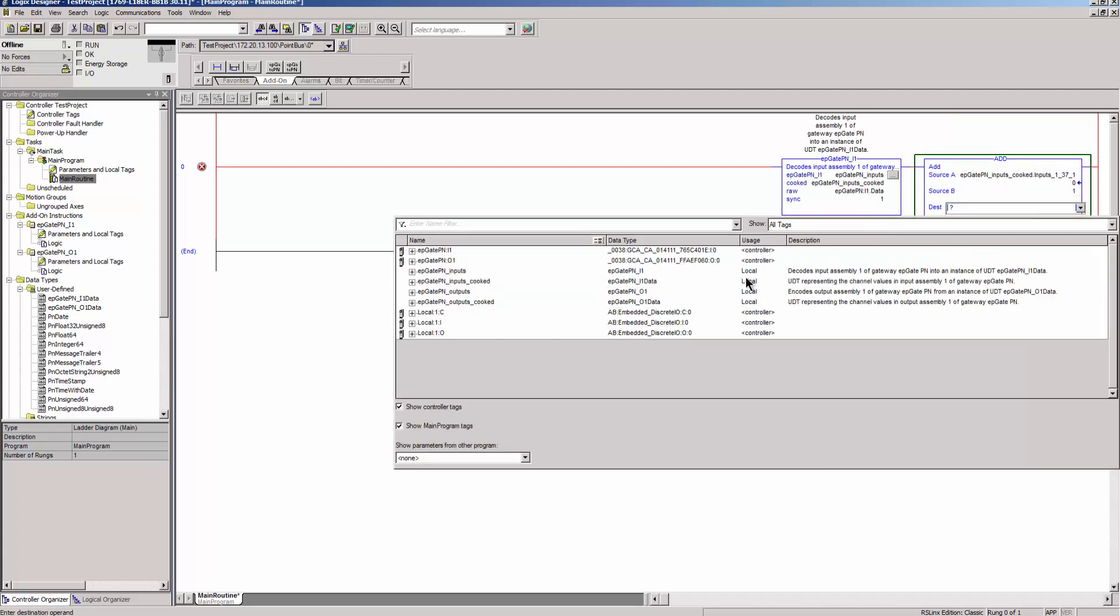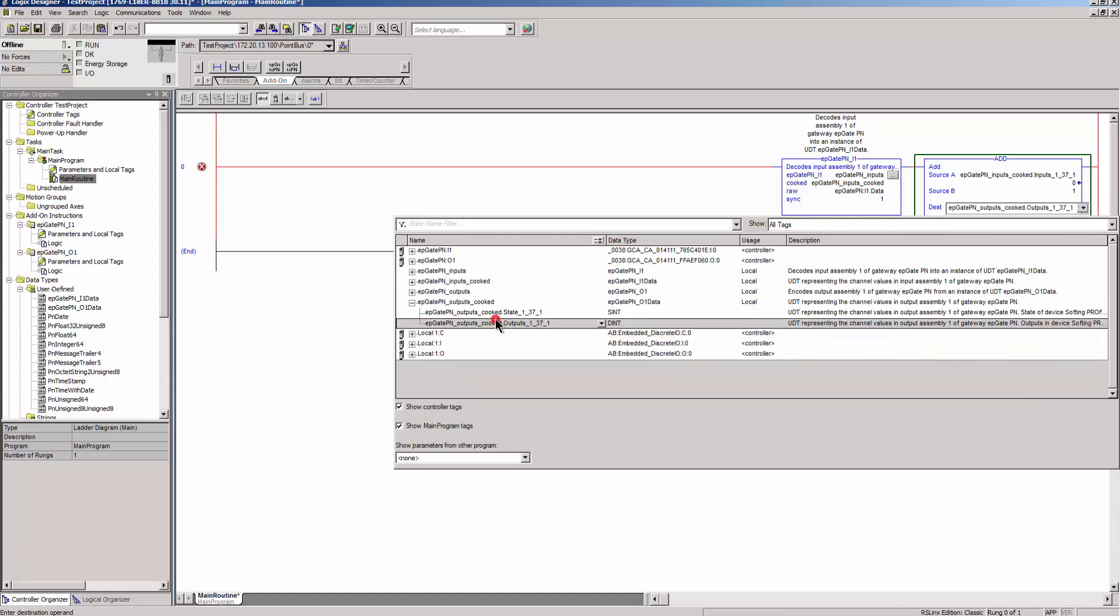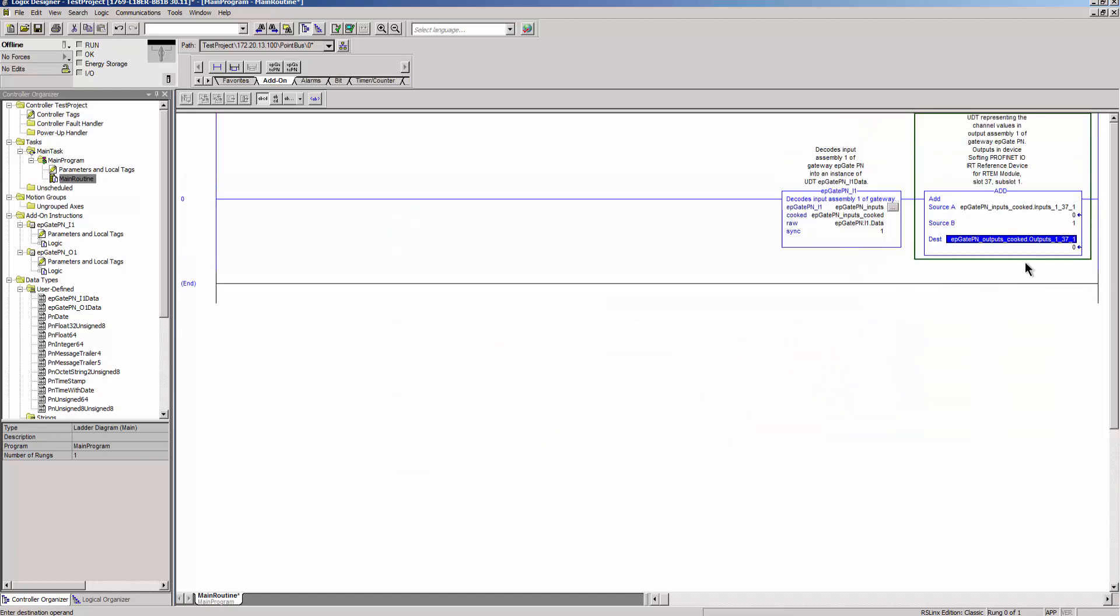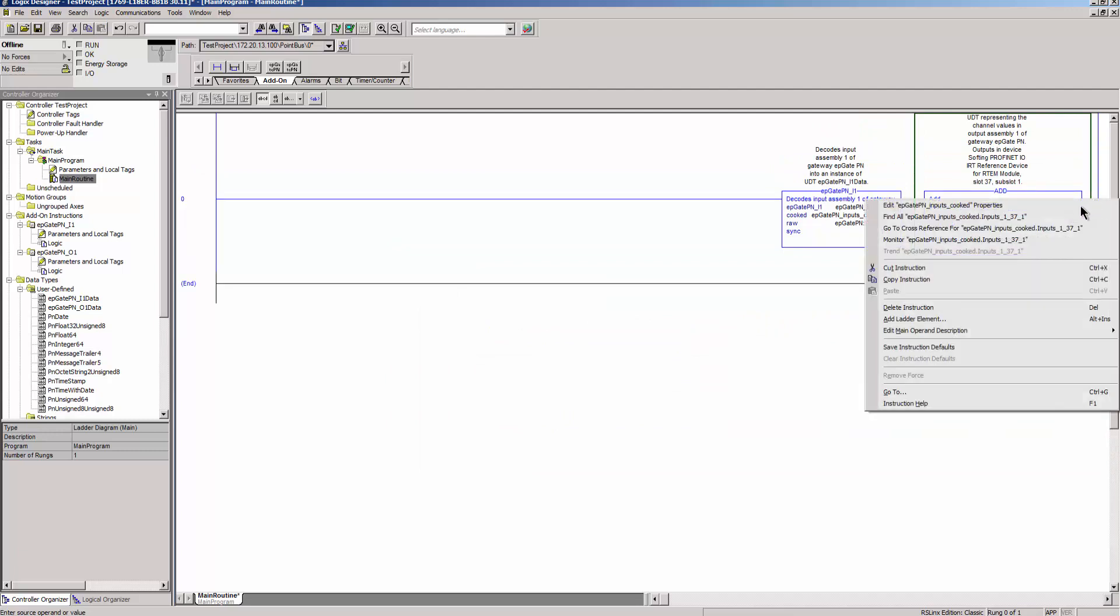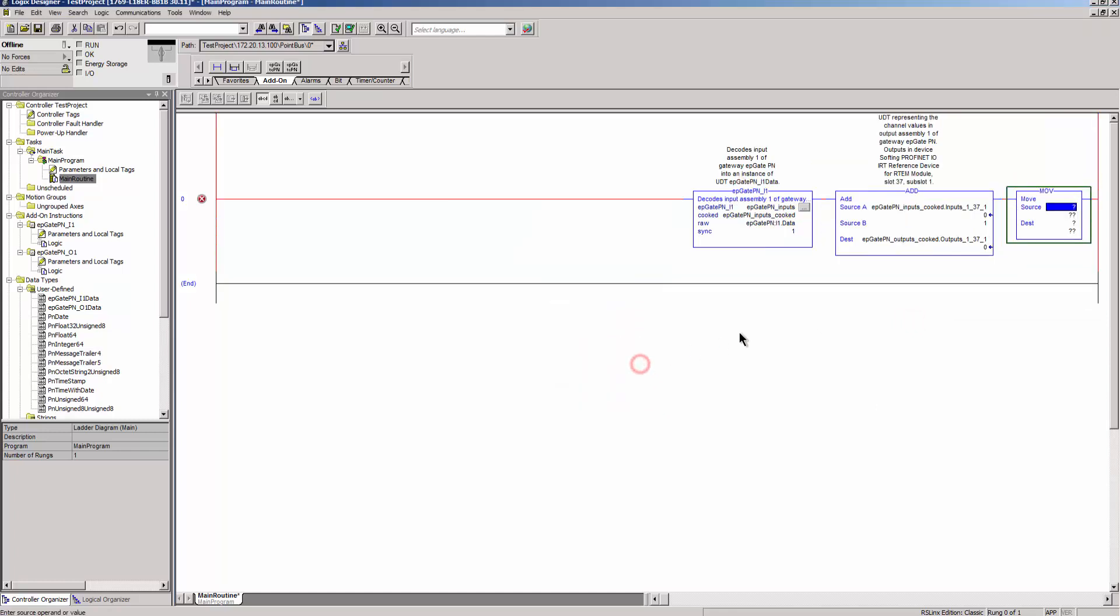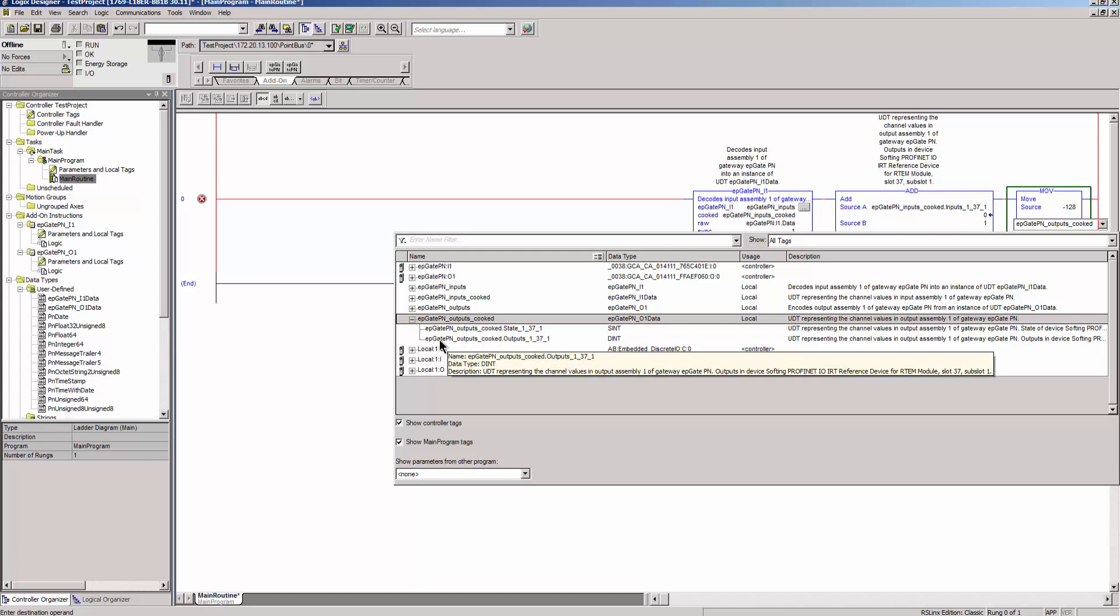In order for the output data to be sent to the PROFINET device, the data status must be set to Valid. To do this, select the MOV block via Add Ladder Element and enter 128 under Source. Under Dest, select the status of the exit data. Now, the output data can be written.